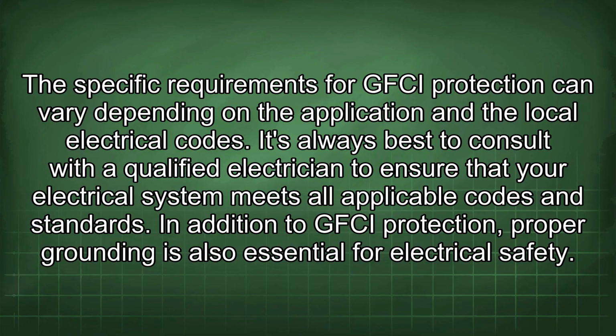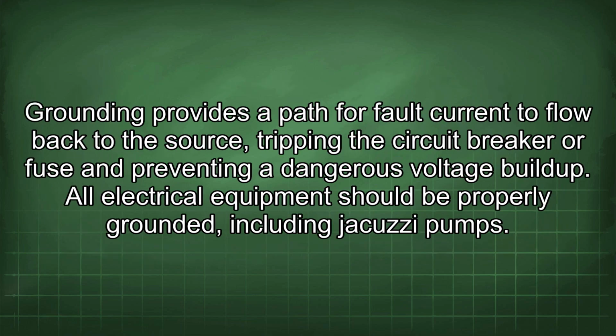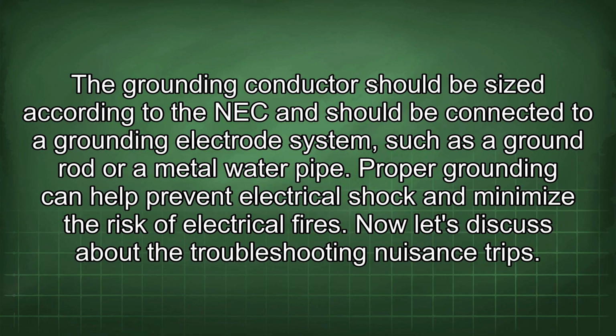standards. In addition to GFCI protection, proper grounding is also essential for electrical safety. Grounding provides a path for fault current to flow back to the source, tripping the circuit breaker or fuse and preventing a dangerous voltage buildup. All electrical equipment should be properly grounded, including jacuzzi pumps. The grounding conductor should be sized according to the NEC and should be connected to a grounding electrode system, such as a ground rod or a metal water pipe. Proper grounding can help prevent electrical shock and minimize the risk of electrical fires.